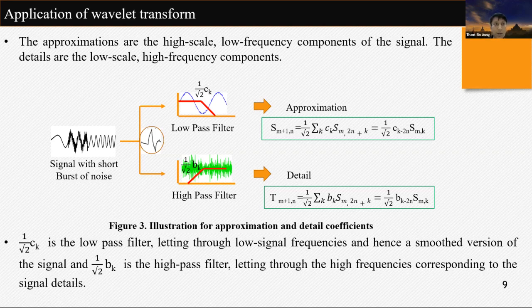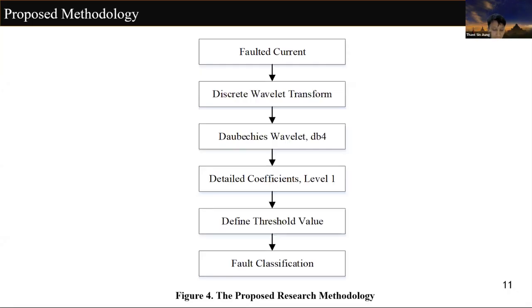And this slide shows the proposed methodology. When a fault occurs on the power system, the voltage and current values increase rapidly depending on the fault resistance. In this paper, only the fault-associated current values are used to classify the fault type. The fault current is transformed to different frequency bands by using a discrete wavelet transform.